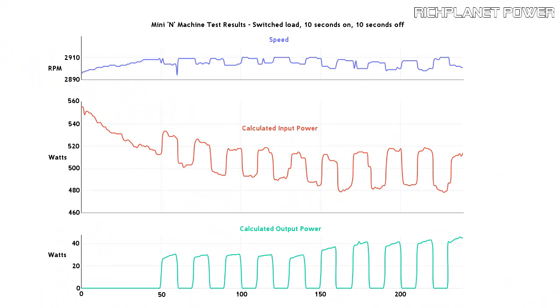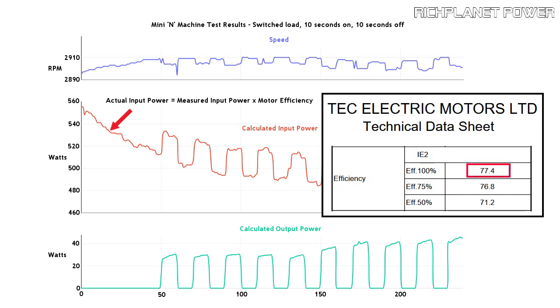The results were then plotted on a graph. Now note that the efficiency of the motor at full load is stated at 77.4%. So this means that the actual power transmitted to the generator via the shaft is 77.4% of the value measured on the power meter. Therefore, this was adjusted before plotting the graph.